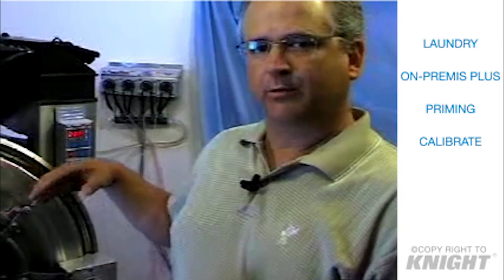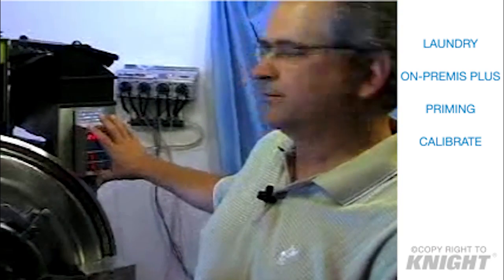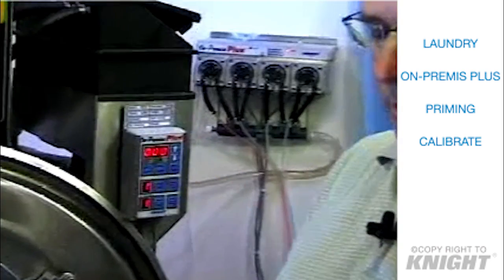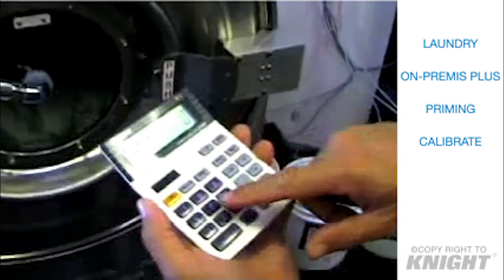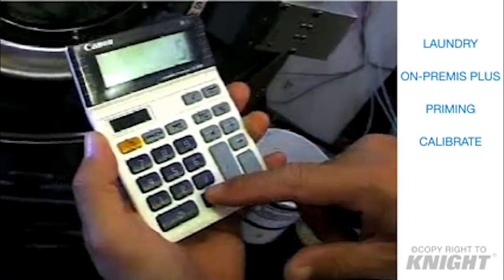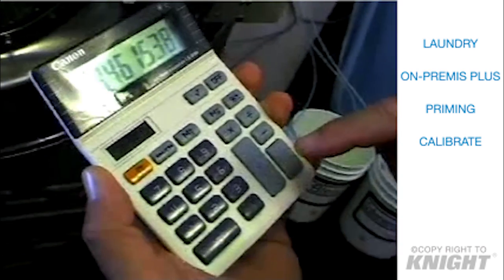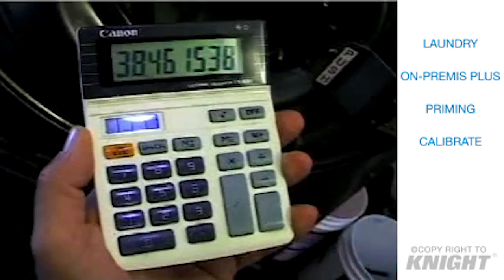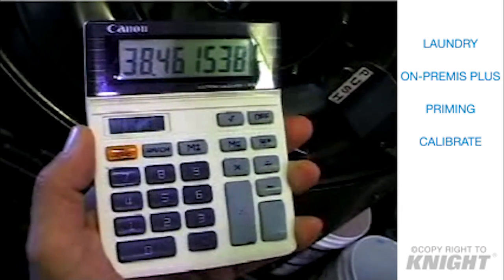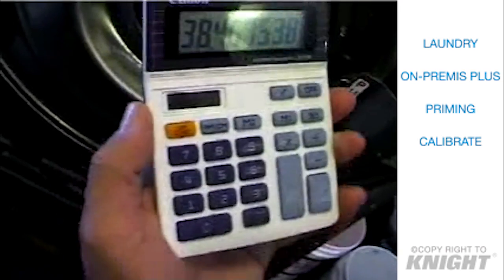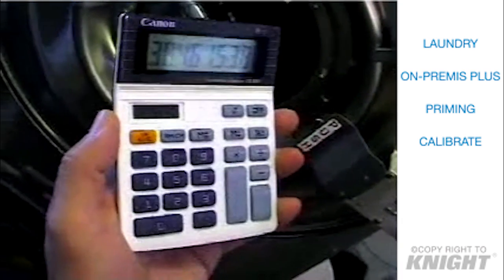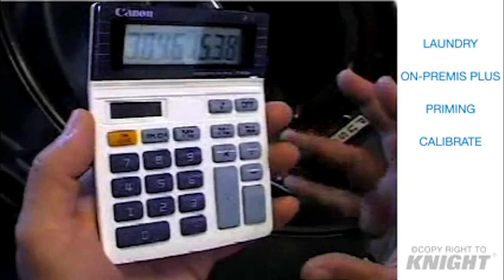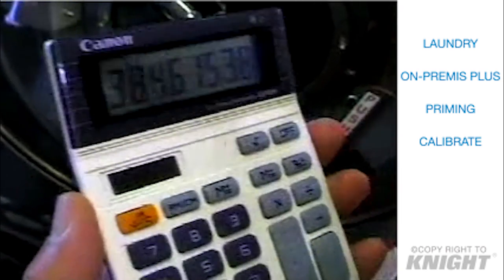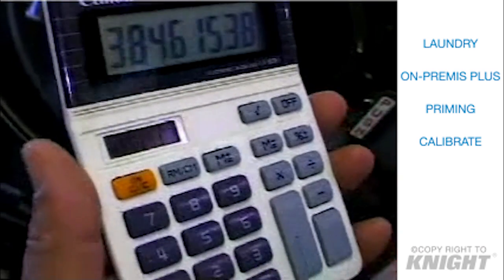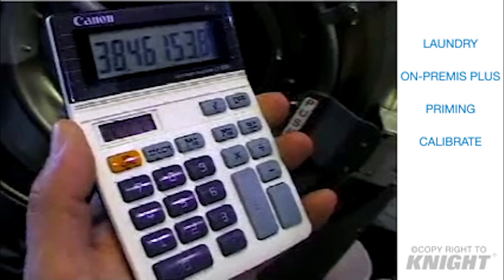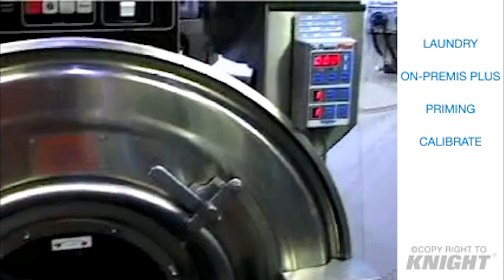In order to achieve the delivery that we want in that particular formula, let's say Formula 1 for sheets, we're going to take 5 ounces and divide that by 0.13. And that will give us a 38.46 second run time for our pump. Now once you have established what your flow rate is for each pump, then the math is very simple and you can program your pump delivery times in the same manner. The other method that we use is the automatic calibration, and we'll show you that technique in review right now.